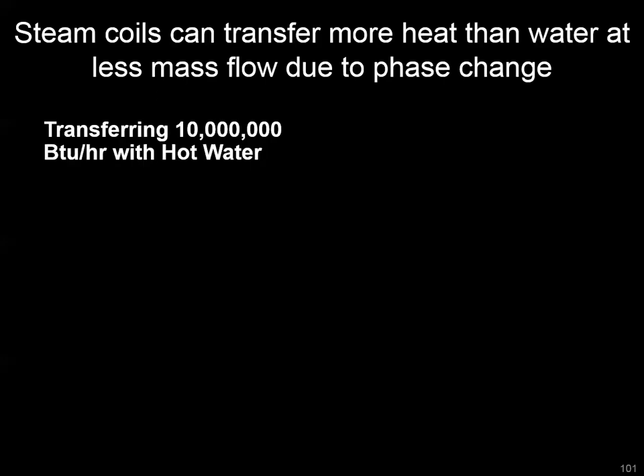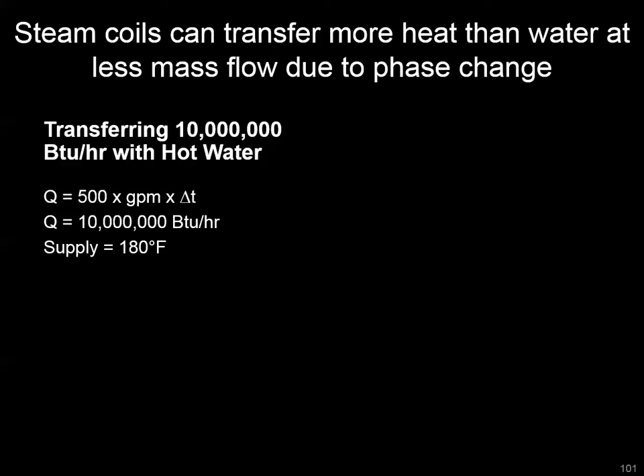Why might you want to use steam versus hot water? Like we saw with cooling system configurations, you're able to move a lot more heat energy with a phase change. To throw some numbers at that — say we wanted to accomplish 10 million BTUH with a hot water system. Using the heat exchange equation for water at typical HVAC conditions and saying we wanted to meet that 10 million BTUH load, we'd probably supply water at about 180°F returning at about 160°F, giving a delta T of around 20°F. That would put the flow at 1,000 gallons per minute.